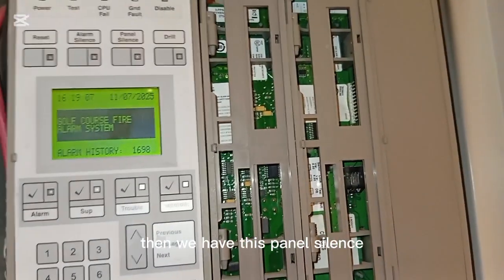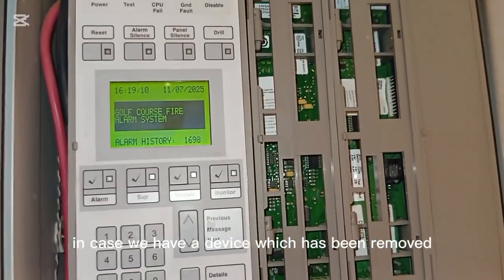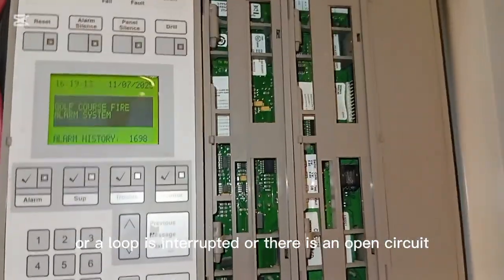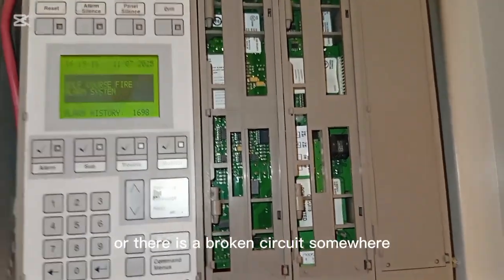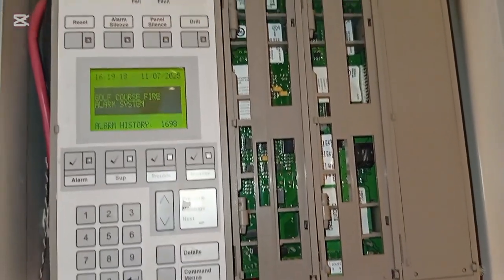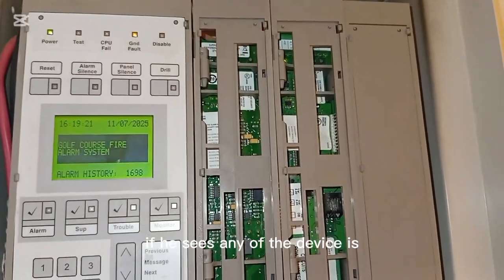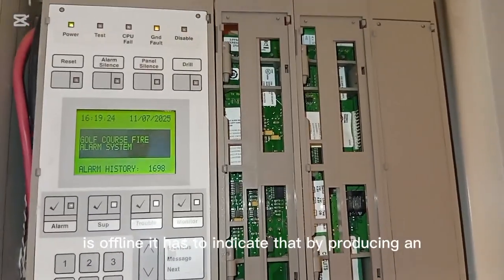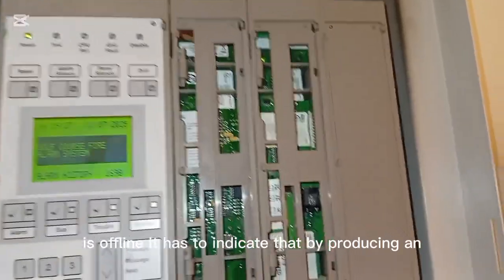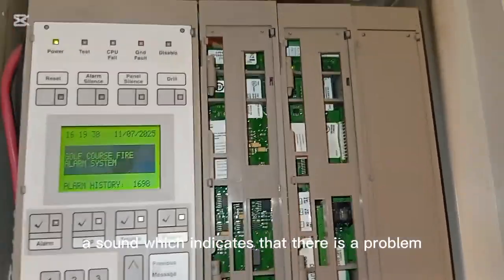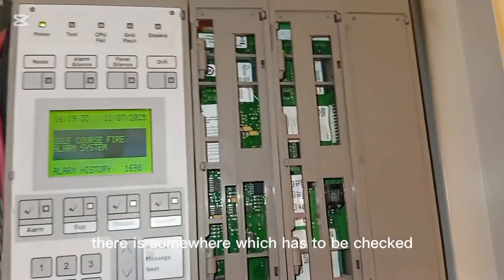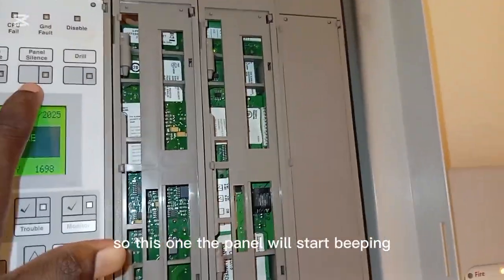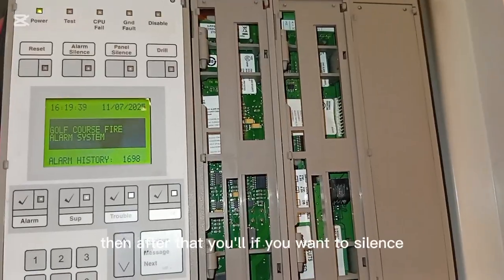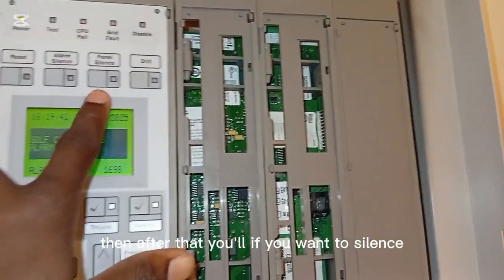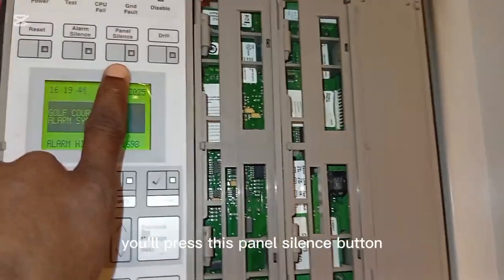Then we have this panel silence. In case we have a device which has been removed, or a loop is interrupted, or there is an open circuit, or a broken circuit somewhere, or a device is faulty, the panel is designed in a way that if it sees any device is offline, it has to indicate that by producing a sound which indicates that there is a problem, there is somewhere which has to be checked. So the panel will start beeping. After that, if you want to silence it, you will press this panel silence button, so the panel will go off. Then we have this fire drill.